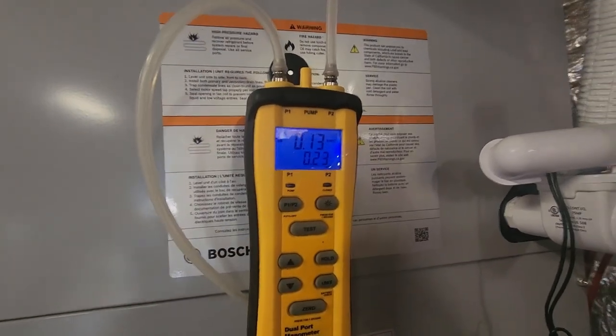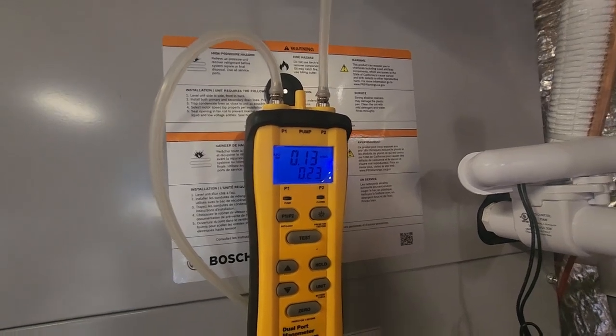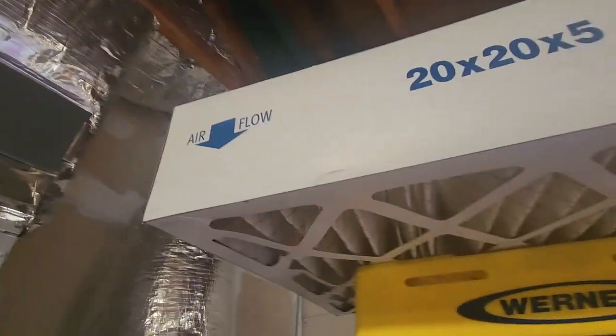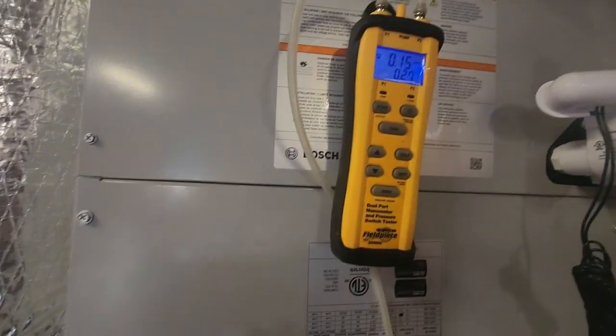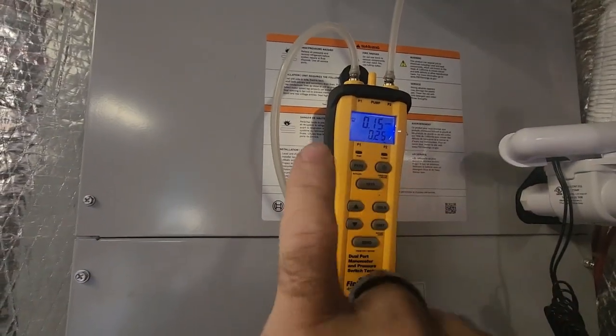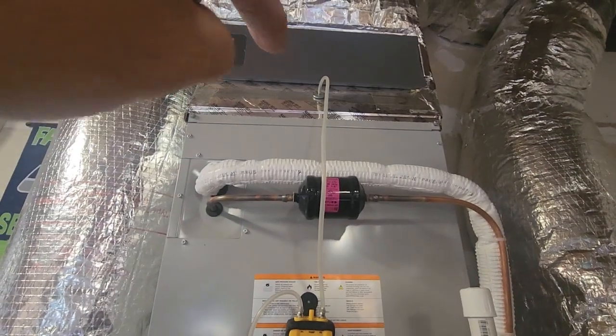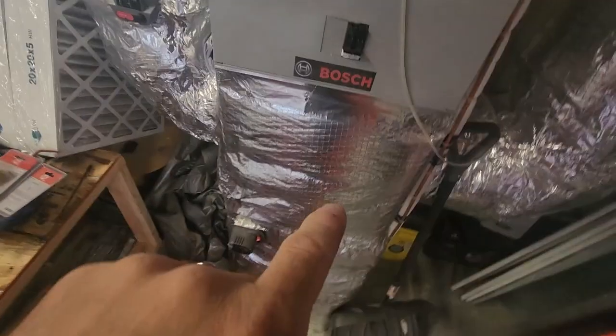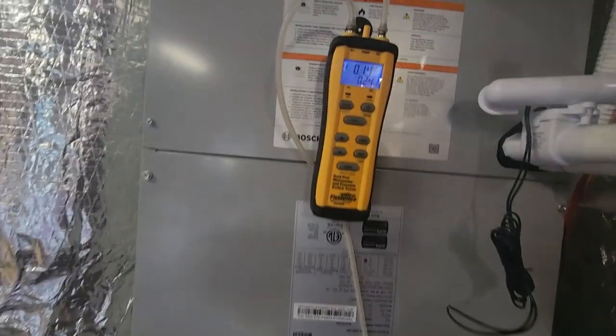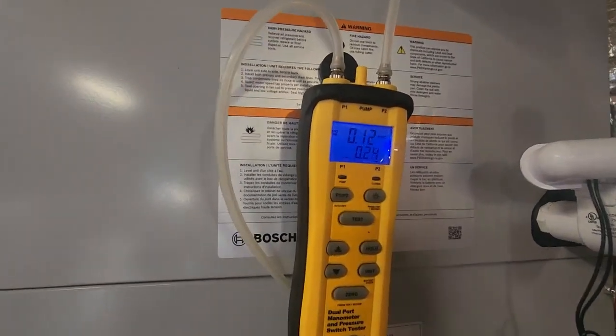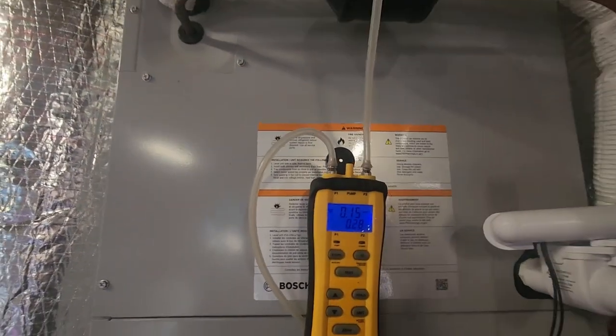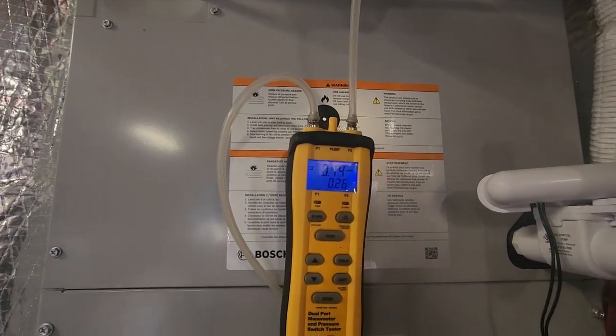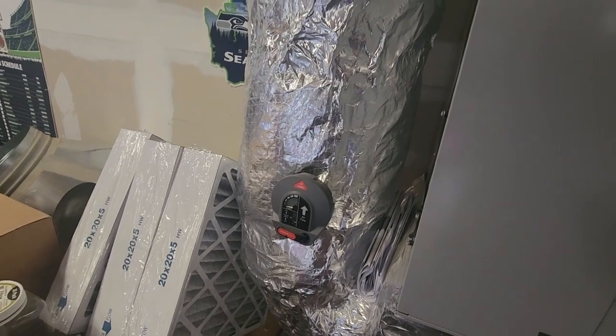Yeah, let's put it on second stage. All right, there's our second stage, both zones open, and the filter's still out. Obviously, when you're doing a conventional system, you're just going to do your supply and return. I recommend taking your readings in a couple different spots, because it's going to vary a little bit. That's why these spacers are important on your return. You want to get between the filter and your air handling equipment. Do it in a couple different spots and take an average, and that'll get you pretty close to your actual static pressure. But look at those numbers, 0.29 total. With that filter in, it's about 0.4-ish, so that's pretty awesome. That's why this bypass damper here never opens.